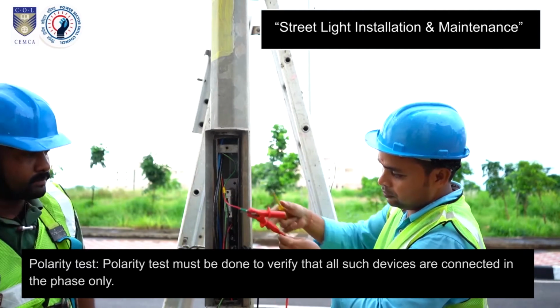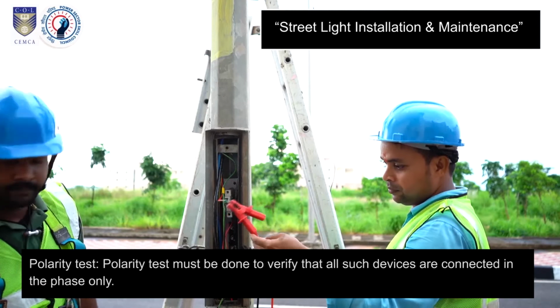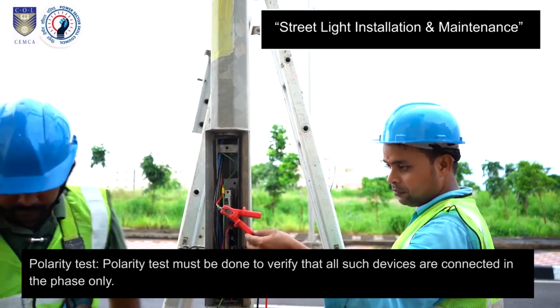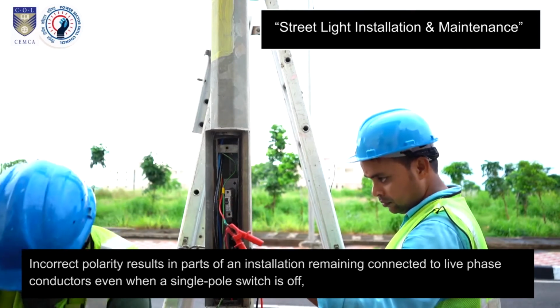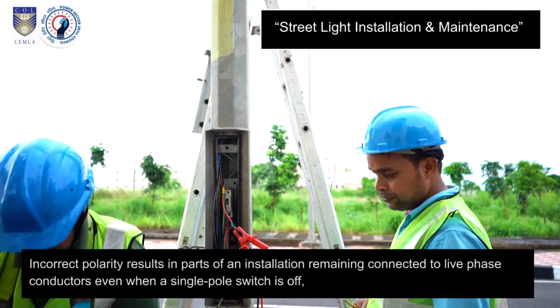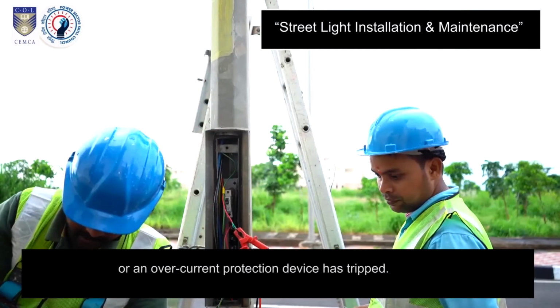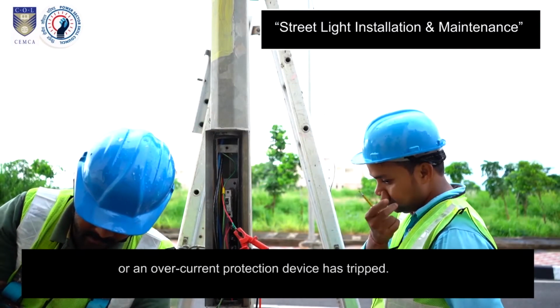Polarity test. Polarity test must be done to verify that all such devices are connected in the phase only. Incorrect polarity results in parts of an installation remaining connected to live phase conductors even when a single pole switch is off, or an overcurrent protection device has tripped.